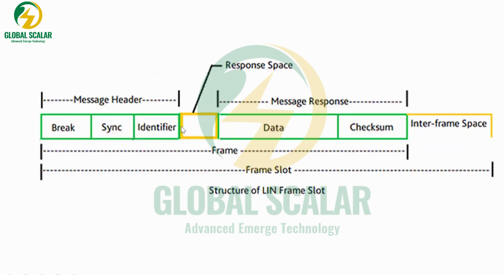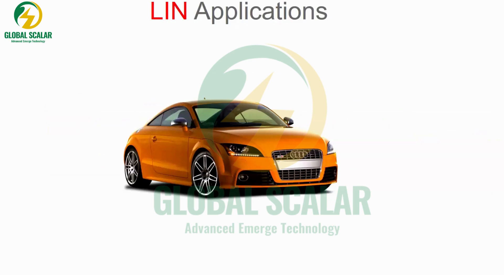Between the message header and message response there is a response space. Together, these are called a frame. Between two messages there is an interframe space. The interframe space, message header, response space, and message response are all together called a frame slot — this is the complete structure of how data is transferred from master to slave.